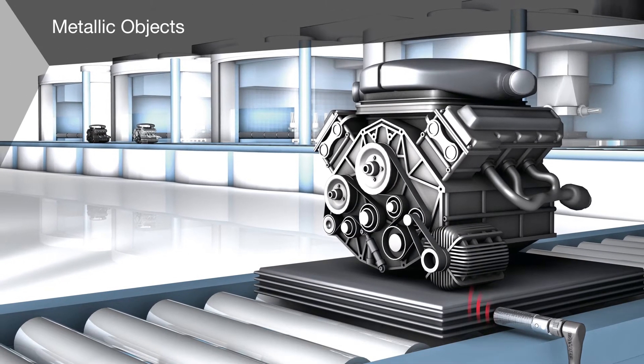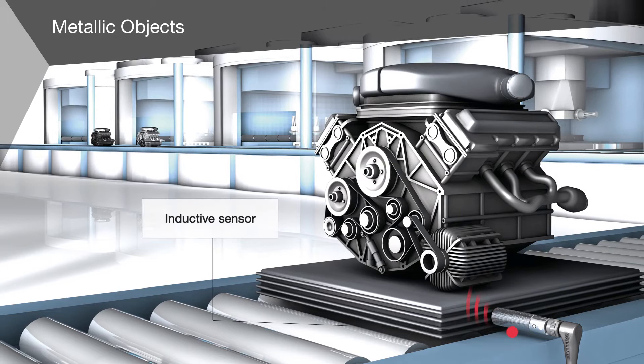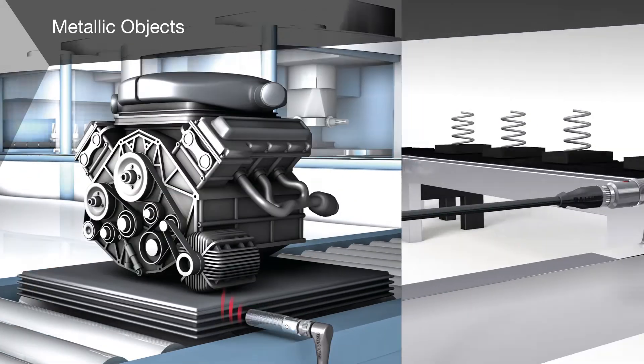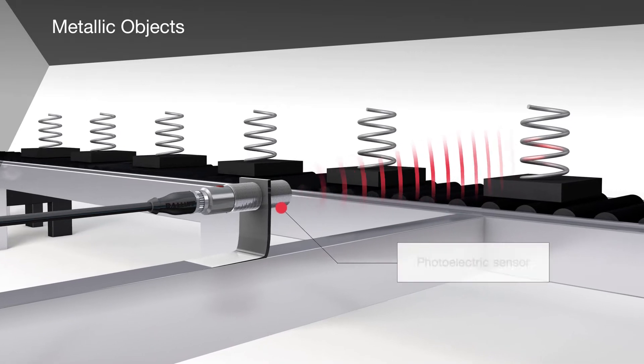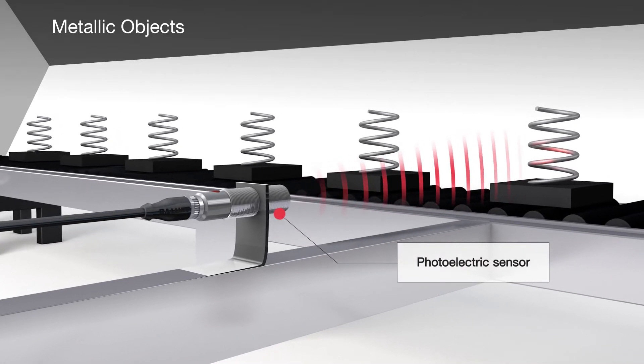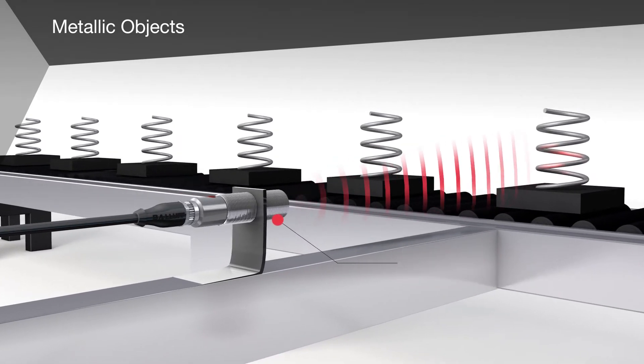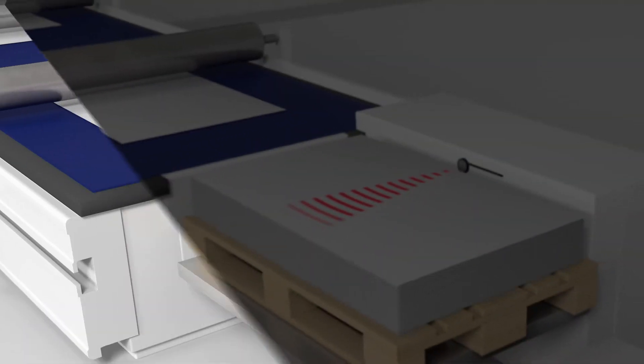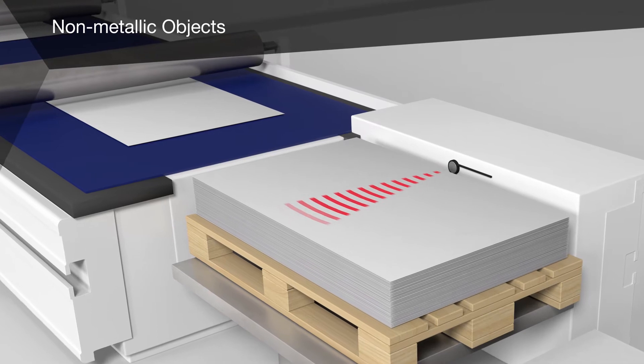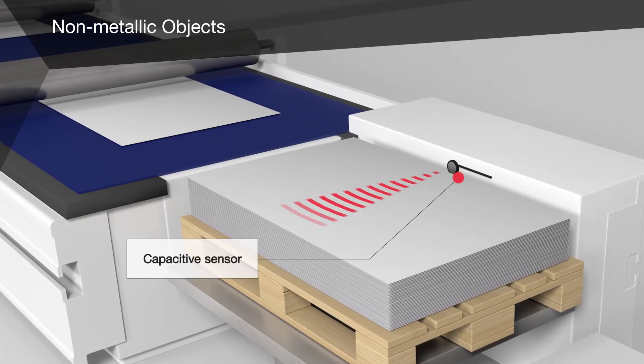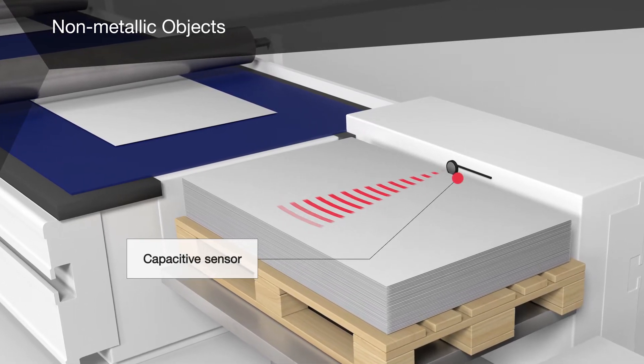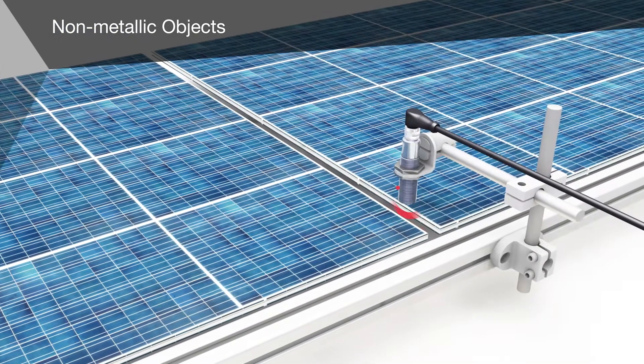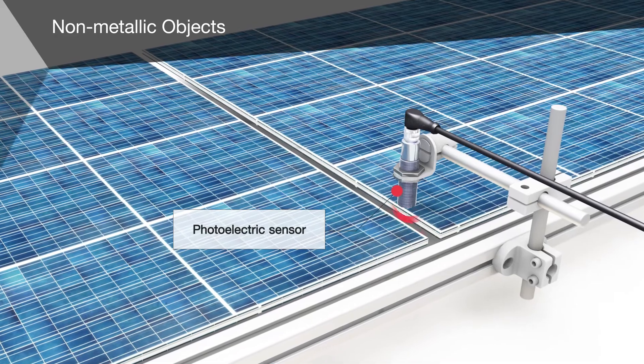Metallic objects can be detected, for example, using an inductive sensor — seen here detecting the workpiece carrier as it passes by — or using a photoelectric sensor which detects the passing steel springs. For non-metallic objects, a capacitive sensor is available, used here to detect the paper stack height, or a photoelectric sensor whose task is to detect the photovoltaic cells.